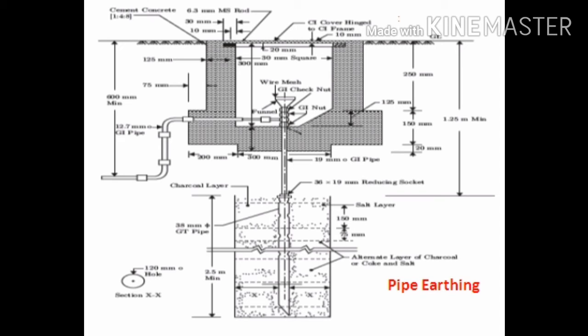In this method, under the ground, from a depth of 1.25 meter to 3.75 meter, a cuboidal pit of 300 millimeter by 300 millimeter by 2.5 meter is dug. In this pit, a GI pipe of 38 millimeter in diameter and 2.5 meter in length is placed vertically. Around this pipe, layers of salt and charcoal of height 150 millimeter are laid.